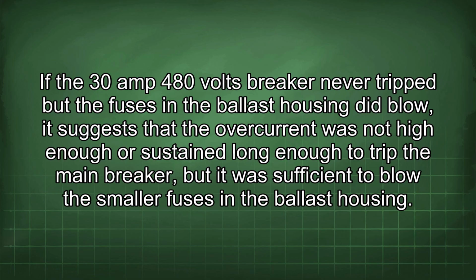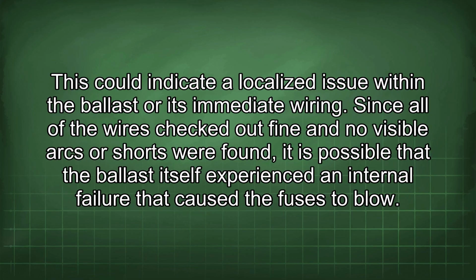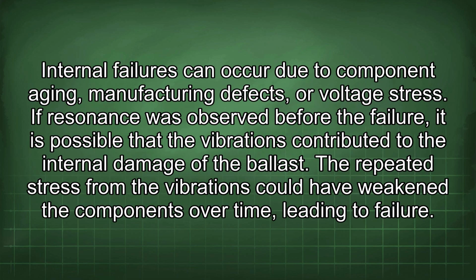If the 30A 480 volts breaker never tripped but the fuses in the ballast housing did blow, it suggests that the overcurrent was not high enough or sustained long enough to trip the main breaker, but it was sufficient to blow the smaller fuses in the ballast housing. This could indicate a localized issue within the ballast or its immediate wiring. Since all of the wires checked out fine and no visible arcs or shorts were found, it is possible that the ballast itself experienced an internal failure that caused the fuses to blow. Internal failures can occur due to component aging, manufacturing defects, or voltage stress.